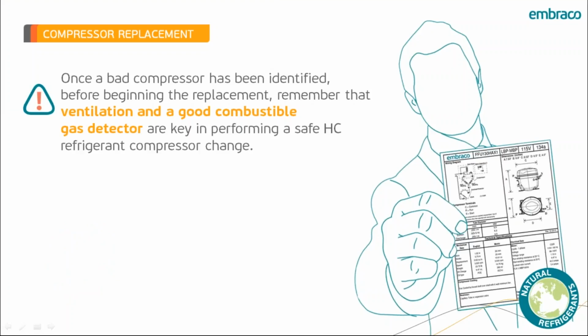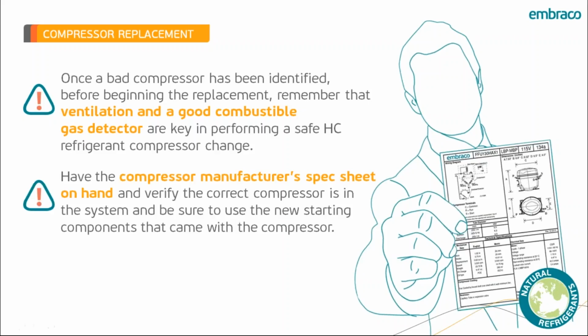So once we have identified a bad compressor, before beginning the replacement, remember that ventilation and a good combustible gas detector are key in performing a safe hydrocarbon refrigerant compressor change. Go ahead and have the compressor manufacturer spec sheet on hand and verify that the correct compressor is in the system, and be sure to use the new starting components that came with the compressor.